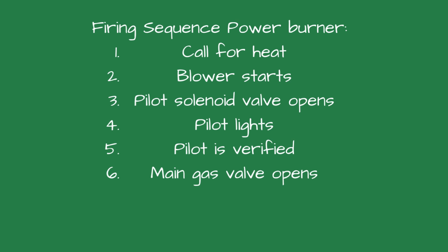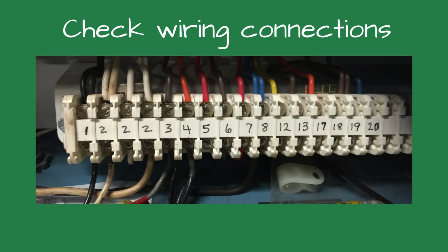On a power burner, you have a call for heat. The blower starts, and that enters the pre-purge phase. You have 4 air changes in the combustion chamber. The pilot solenoid opens, and the spark ignites the pilot. The flame safeguard verifies the pilot within 10 seconds, and the main gas valve opens. In both cases, if the pilot isn't proven within the trial period, typically 10 seconds, the flame safeguard locks out on flame failure. Here's a step-by-step troubleshooting guide.